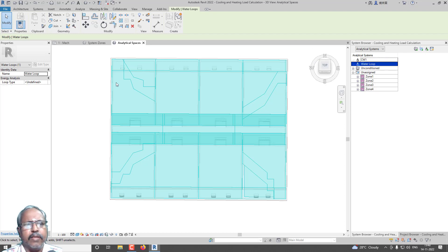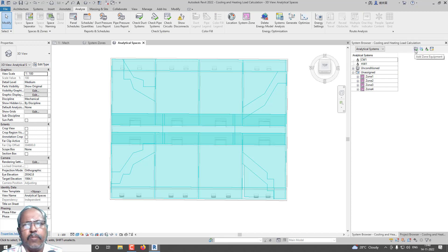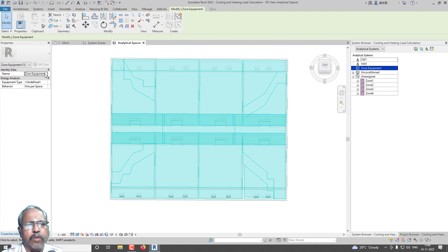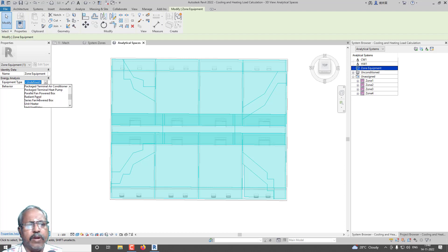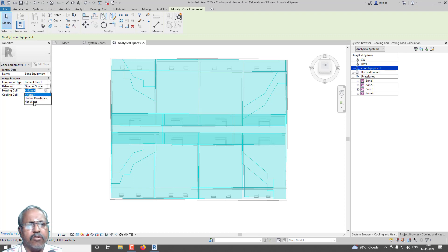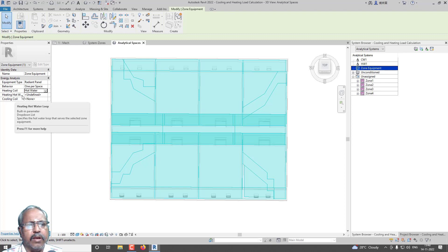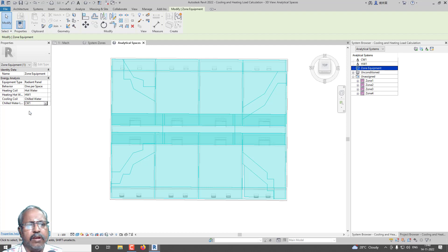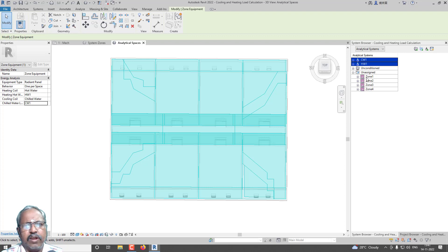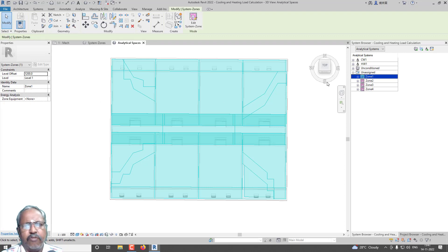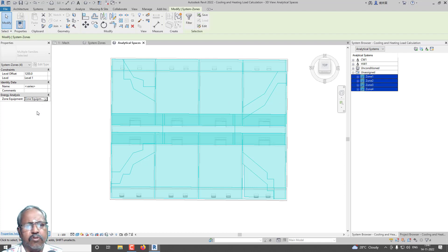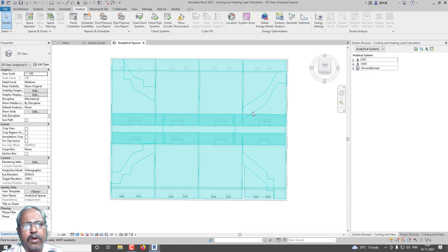Now go for Zone Equipment and click Add Zone Equipment. You can give zone equipment any name or leave it as is. For Equipment Type, I am going to use Radiant Panel, which is simpler. Behavior: one per space. For Heating Coil, select Hot Water — we already created HW1, so select Heating Hot Water Loop HW1. For Cooling Coil, select Chilled Water — we already created CW1. Now select all four zones using Shift-click and change them all to this zone equipment. Now our system is ready for analysis.